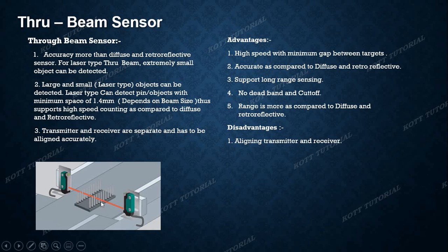This is the most important point over here. If my pin is 10 mm, the laser rays coming from the sensor must be less than 10 mm. If it is greater than 10 mm, it will not work.